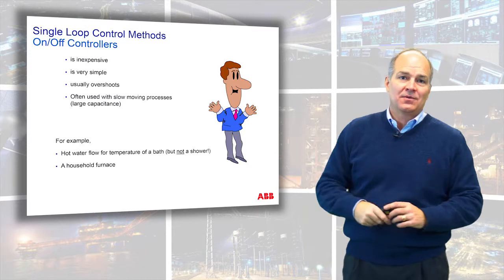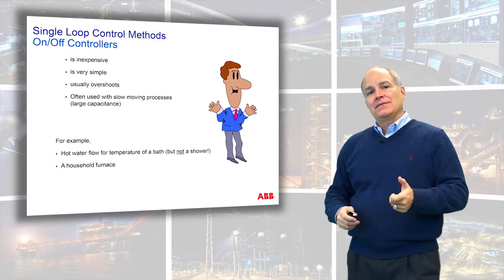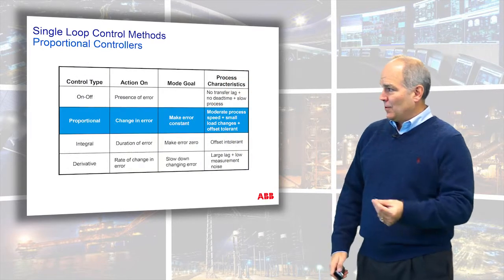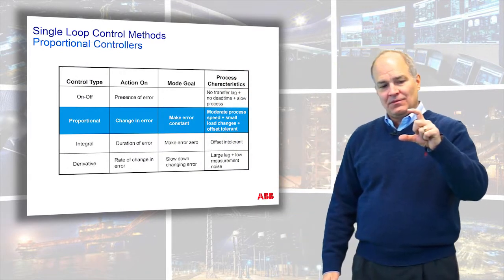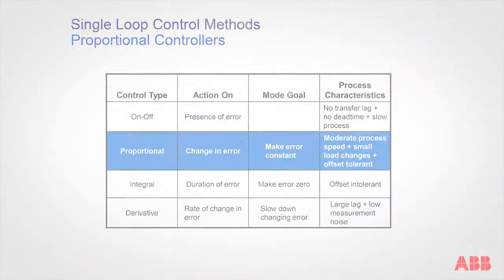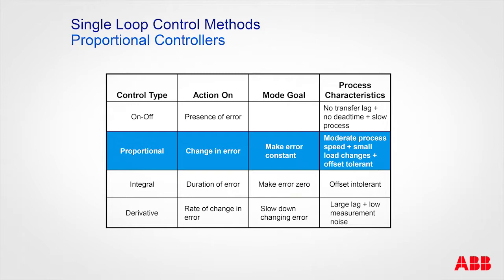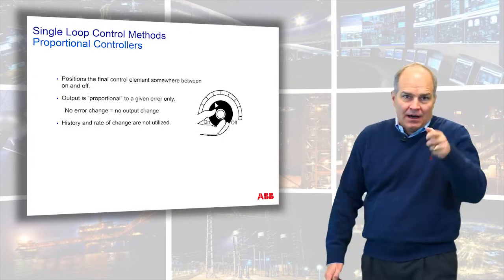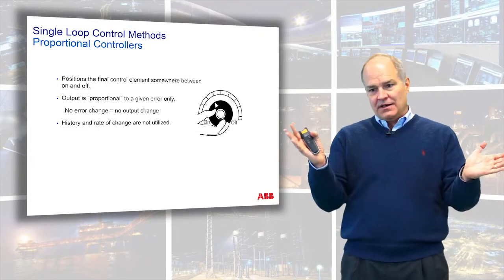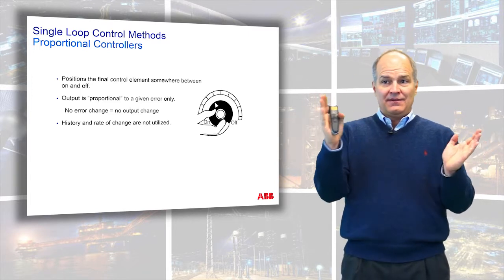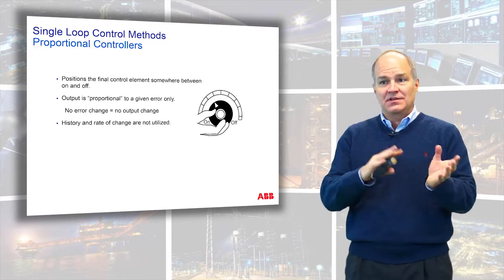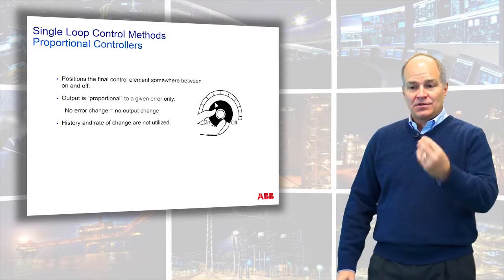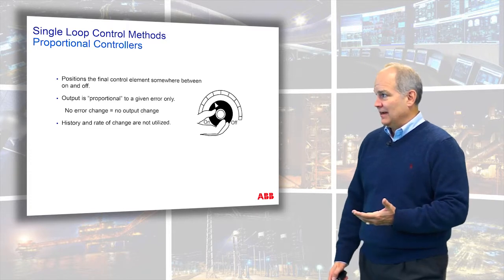If you want to go beyond on-off, that's when we have to start understanding proportional control. Proportional control's goal is to work on the change in error — it's very important to realize its goal is not to make the error zero, but to make the change in error zero. Like a knob, with proportional your output could be somewhere between zero and 100%, so you need an actuation device that allows a variable output.